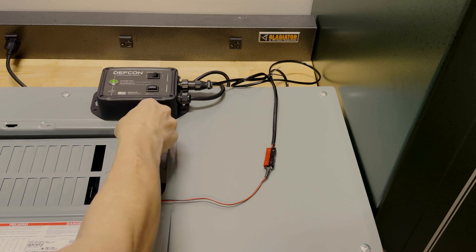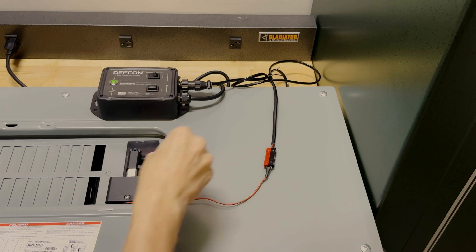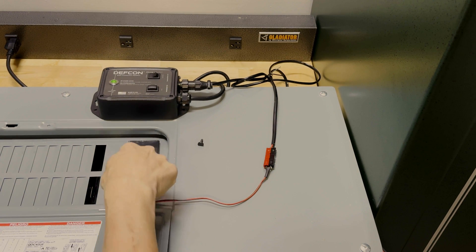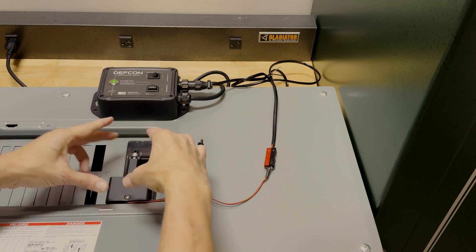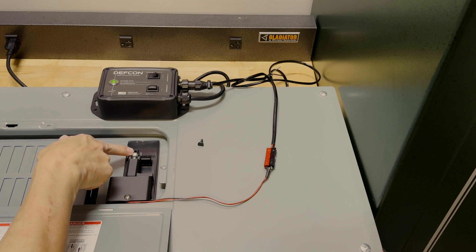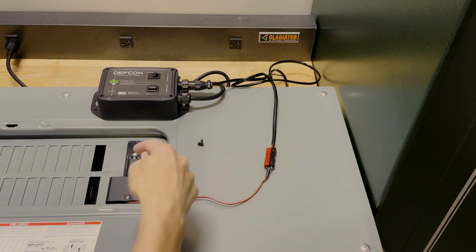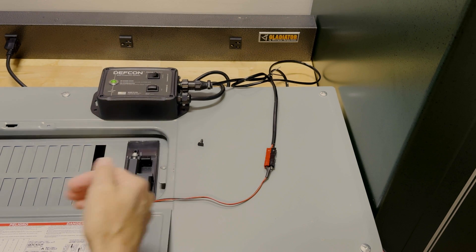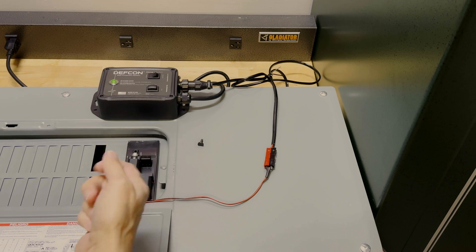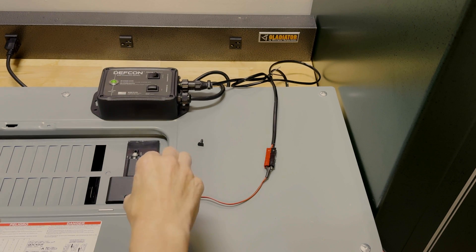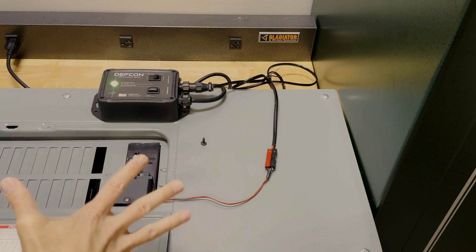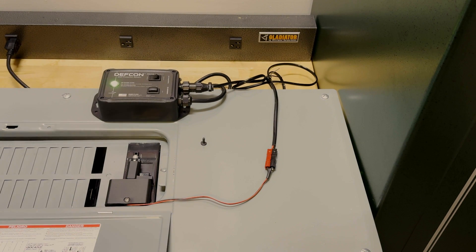So first thing you do is you take out this little pin, a little locking pin at the end of the actuator arm, this little end effector here, and then you just simply compress that end effector down just with your fingers. And you'll notice the actuator arm is still out, so we have to retract that some way. And what we're going to do is we're going to apply power back to the system. We're going to manually retract it. So first thing I've got to do is throw the breaker now since I've moved this arm out of the way. This is a big heavy breaker, but I'll go ahead and get it tripped back. So I tripped the breaker back, so now we have power back in the system. Light comes back on, everything's back operational again.